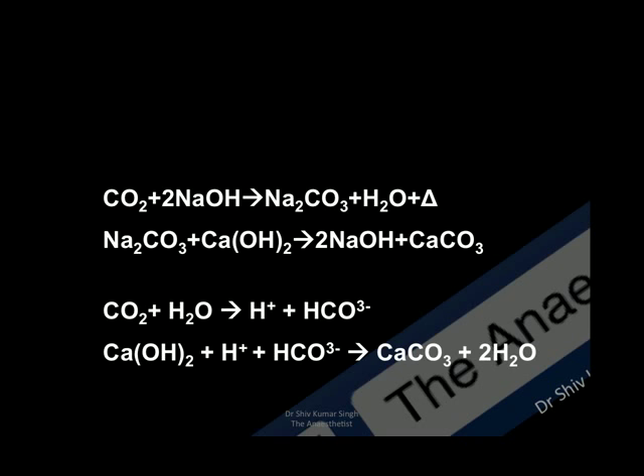It is important to know what reaction occurs in the soda lime when carbon dioxide comes in contact with it. Carbon dioxide reacts with sodium hydroxide to produce sodium carbonate, water, and heat. This reaction is very important for the heating and humidifying of the gases that pass through the soda lime. Sodium carbonate can again react with calcium hydroxide to produce sodium hydroxide and calcium carbonate.